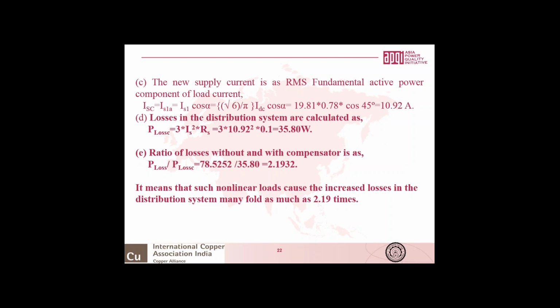The losses in the distribution system are calculated as P loss C equal to 3 IS square into RS, and that is equal to 3 into 10.92 square into 0.1. This becomes 35.80 watt. And the ratio of the losses without and with compensator is now P loss upon P loss C, that is 78.5252 divided by 35.8, and that is 2.1932, the ratio.